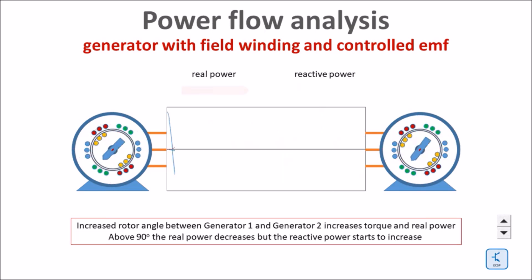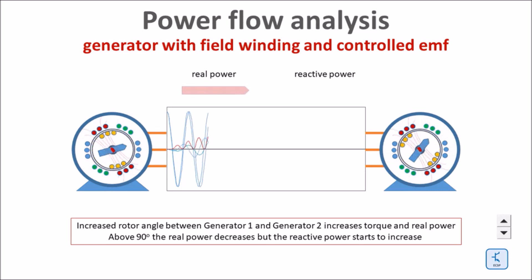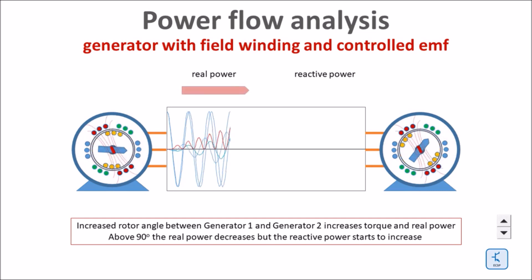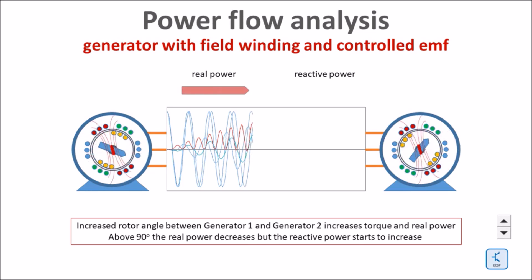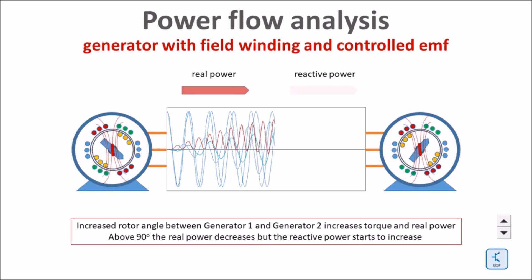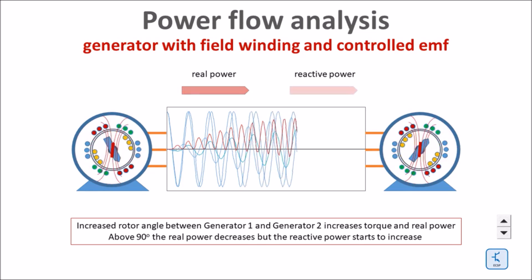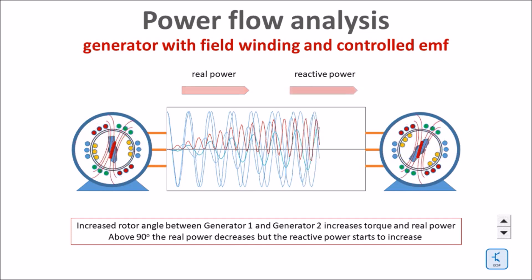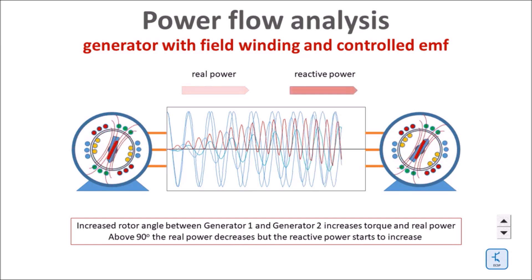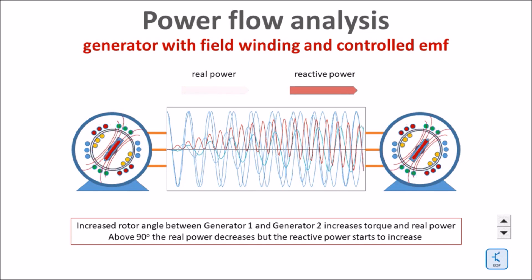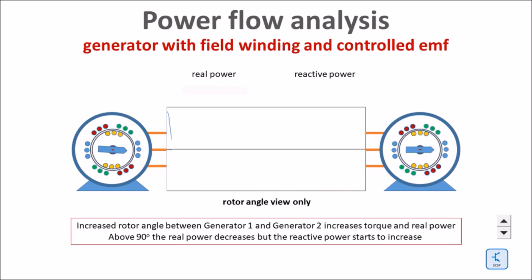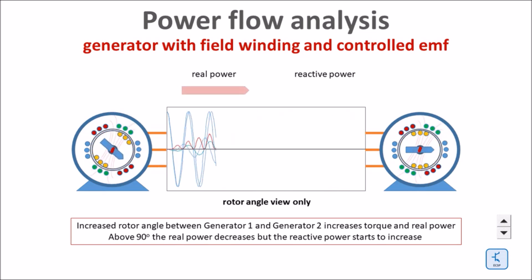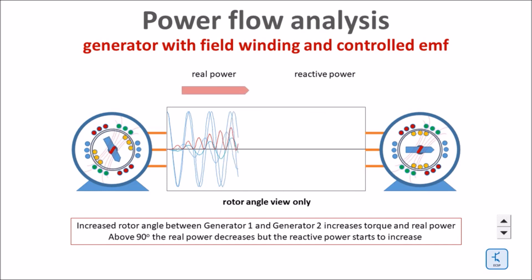Now for the first time we build up an angle between both rotors and guess what, we get real power flowing from the left generator to the right generator. If the right generator angle lags it acts as a motor. In order to make the point I filtered out the rotation so you can see the growing rotor angle in slow motion.